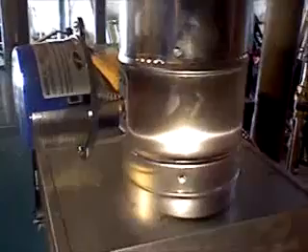Here's our motorized vent damper. This shuts off when the boiler shuts off. It stops the sucking of the heat out of the system. And this box right here is actually for dilution air. So the products of combustion come out of the boiler extremely hot, and then air comes up this way and gets diluted. And here's our flue piping into our chimney.